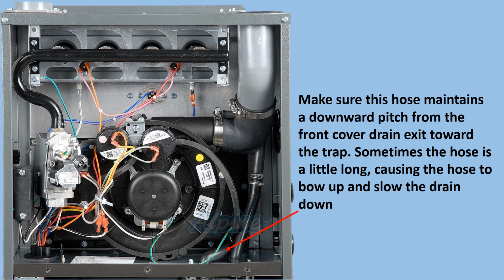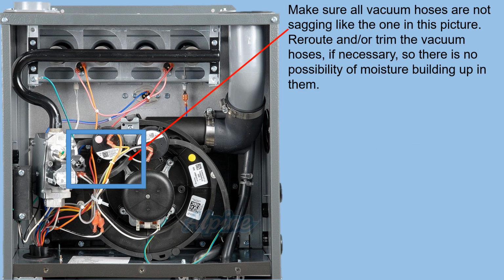Make sure this hose, where the arrow's pointing, maintains a downward pitch from the front cover drain exit toward the trap. Sometimes the hose is a little long, causing the hose to bow up and slow the drain down. It doesn't take much of a bow at all, because there's not a whole lot of pitch there. Make sure all vacuum hoses are not sagging like the one in this picture. Reroute and or trim the vacuum hoses if necessary so there's no possibility of moisture buildup in them.